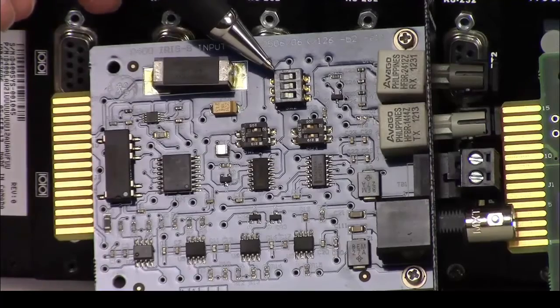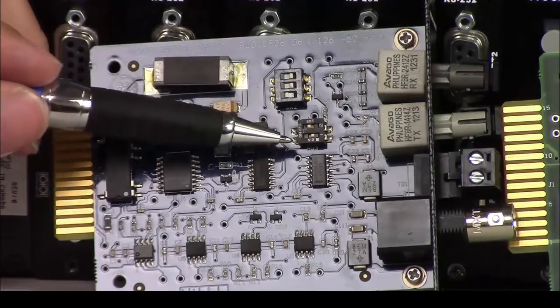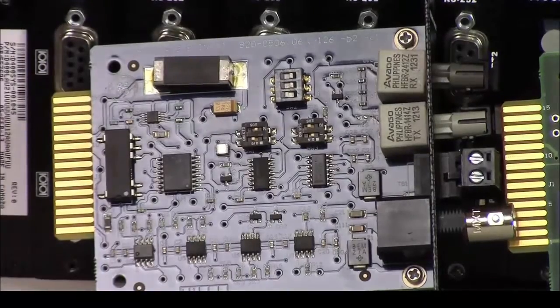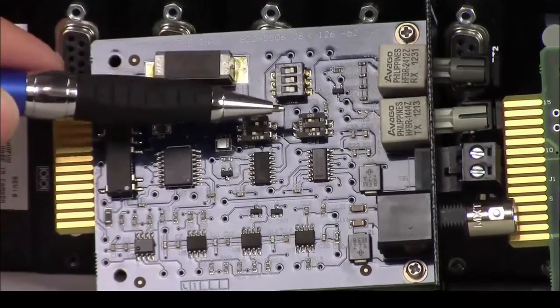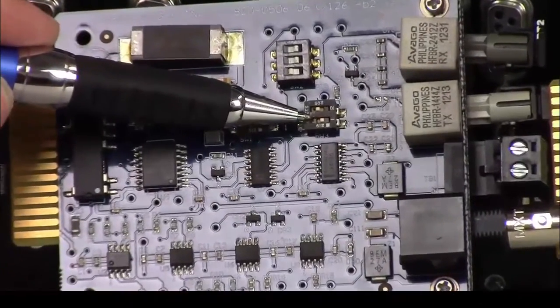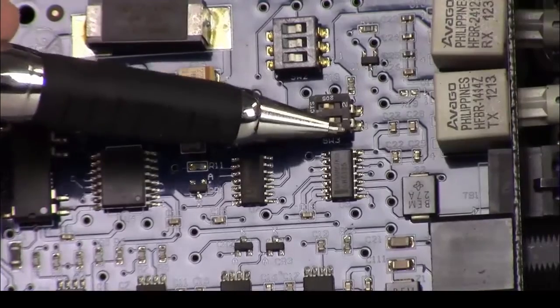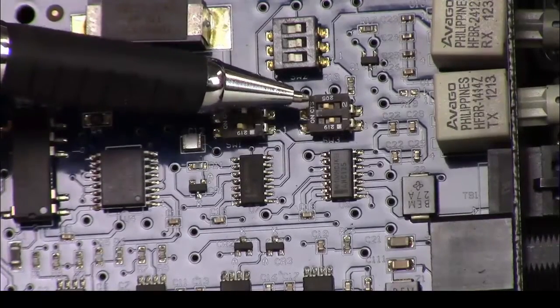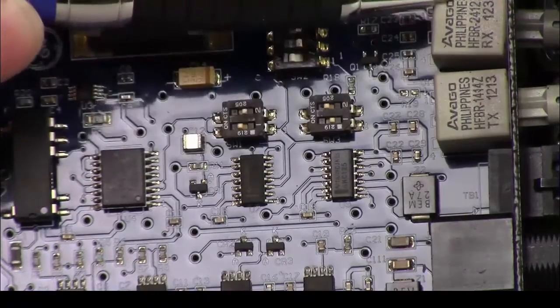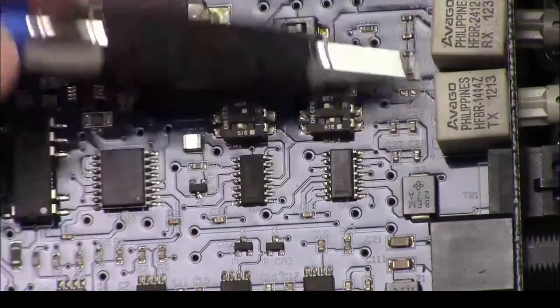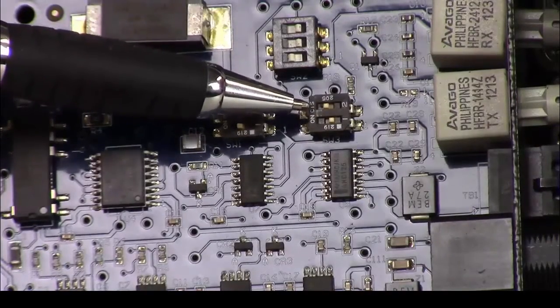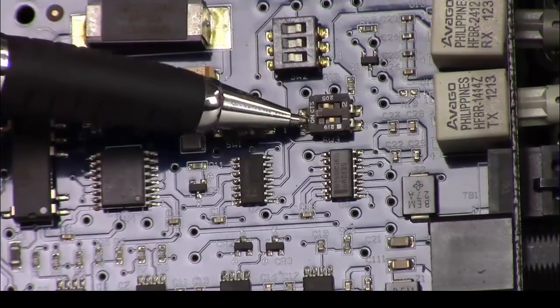So that's it for switch number two. Switch number three basically controls whether we are inverted or normal. If this is received, this is transmit, this would be the setup. So pin number one will be the on position or toward the number, pin number two will be the off position or away from the number. If we want this to be the transmit, this will be the receive, or the inverse of what is the norm on this card. Then switch number one will be to the off position, switch number two will be to the on position.